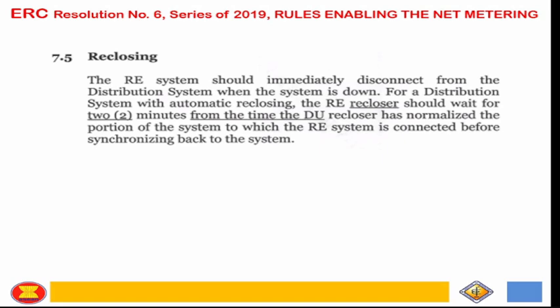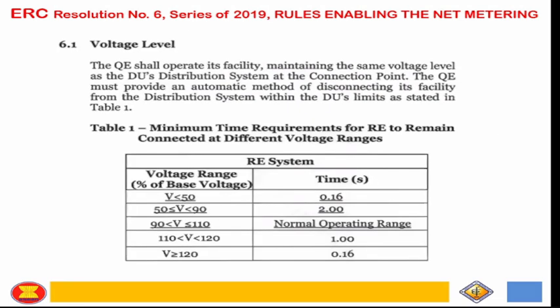Then for the distribution system, automatic reclosing should wait 2 minutes from the time the DU recloser has normalized. So if it's reclosing at 2 minutes, pwede kang papasok, no, magsi-synchronize yung DG, no. So it's actually confusing between the islanding and then the reclosing, but it's different, no. This is a reclosing function. So you can wait after 2 minutes, nga pwede kang mag-synchronize na naman.